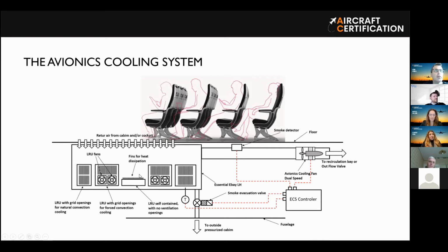Inside the bay, you have several types of electronics. There are electronics that receive only natural convection. There are units that have their own ventilation fans. And there are electronics that have fins for heat dissipation. In all the cases, we will have some airflow to remove the heat load from these electronics, okay? And the outlet will be driven by a cooling fan. The outlet flow can be launched in the outflow valve or can be launched in the recirculation bay.